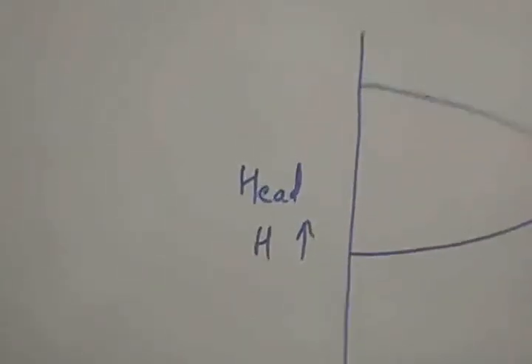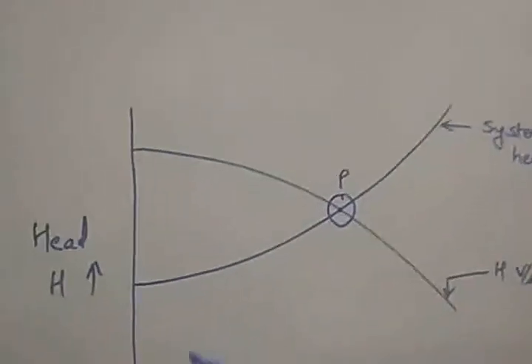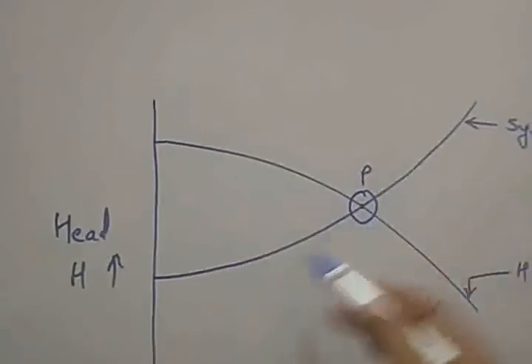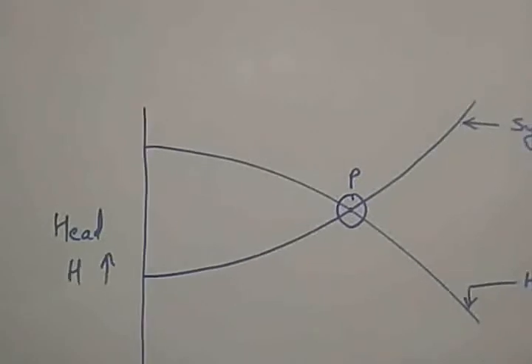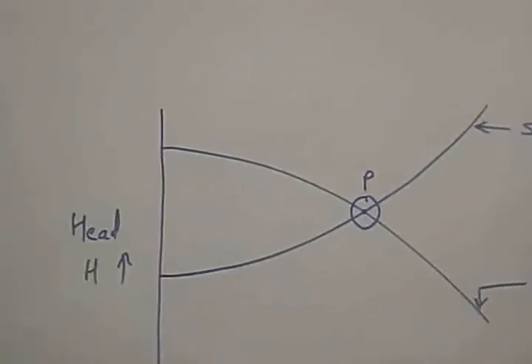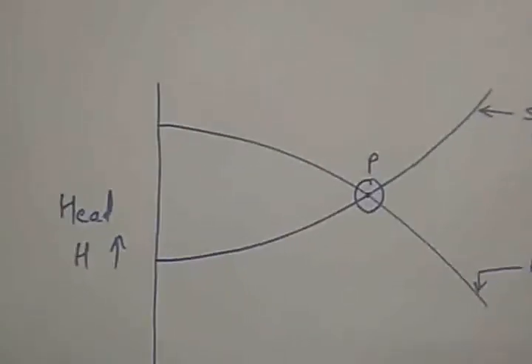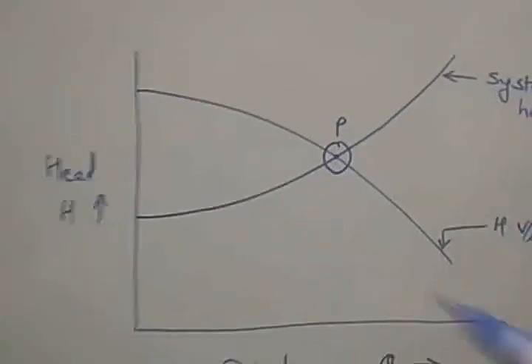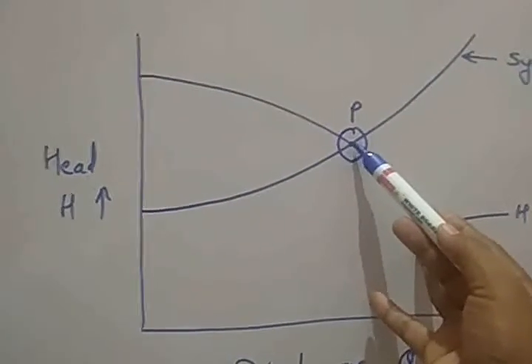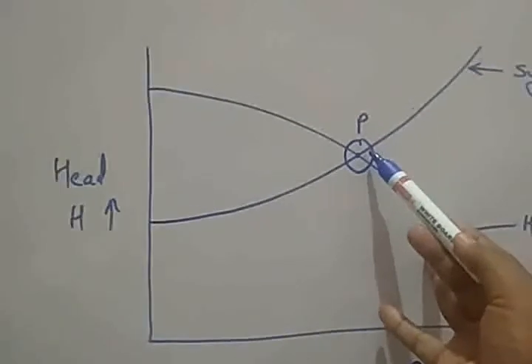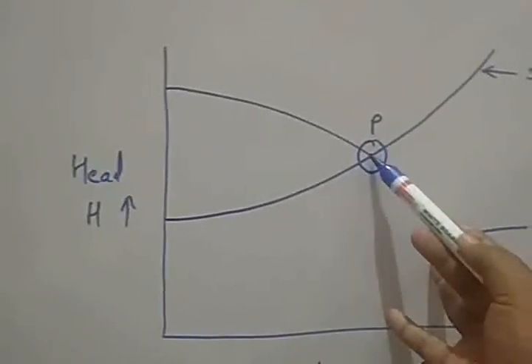The system head curve gives the head demanded by a pumping system for a particular discharge. At point P, the head demanded by the system equals the operating head for that particular discharge. So point P is where head demanded by the system equals the operating head of the pump for a particular discharge.